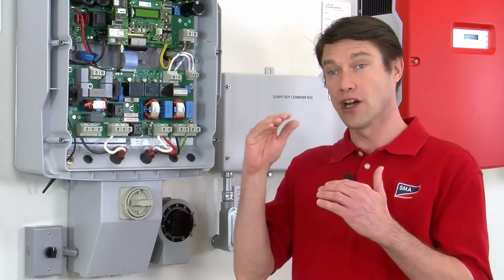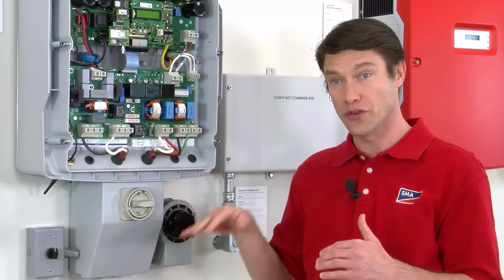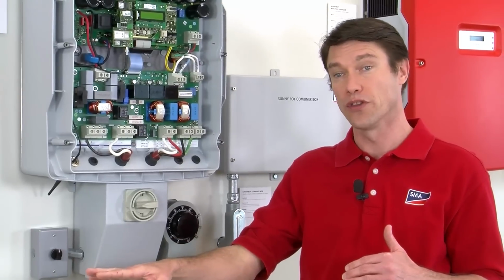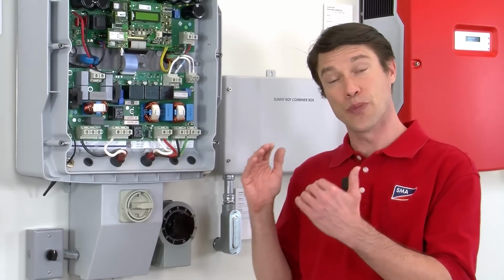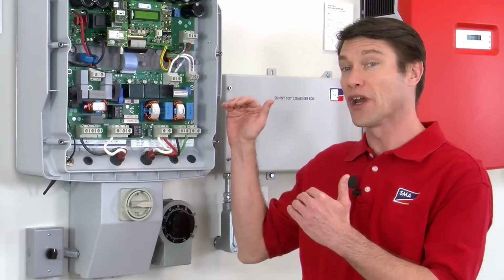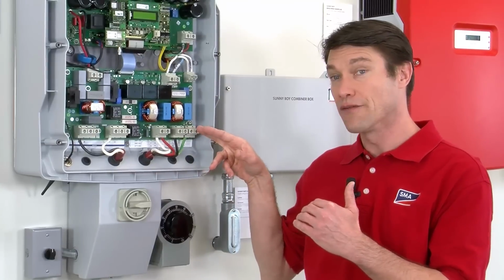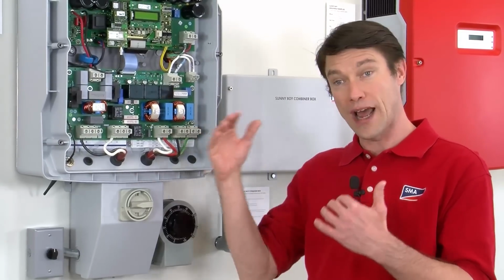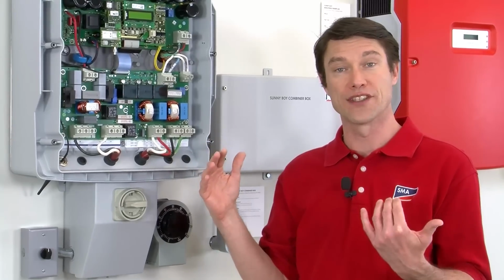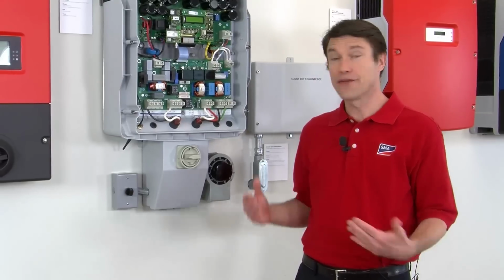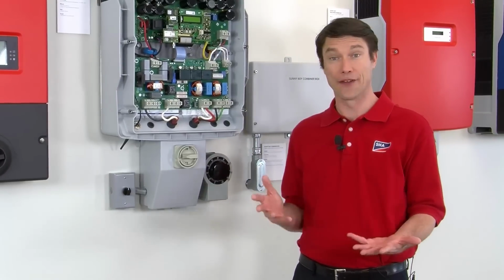So the voltage will have to go up correspondingly out of the inverter to get across that resistor and come onto the utility grid. And if that resistance is big enough, the voltage will go up and up and up on the terminals here, and eventually the inverter will say, I have to go outside of spec, that qualifies as a bad grid, and it gives the VAC error and shuts off. Now, the remedy for the loose wiring is pretty simple, just tighten down the connections.